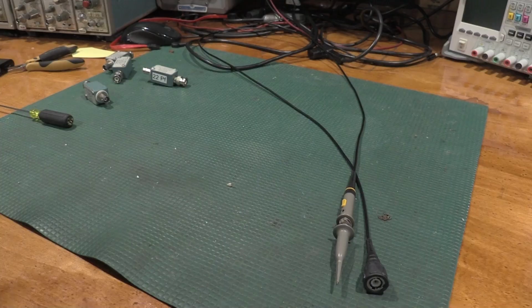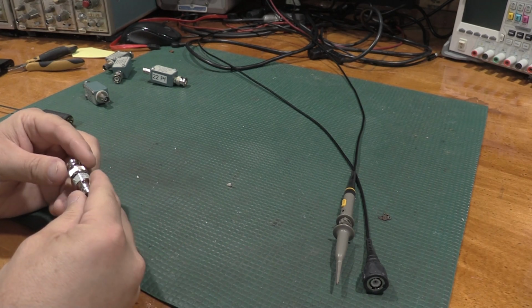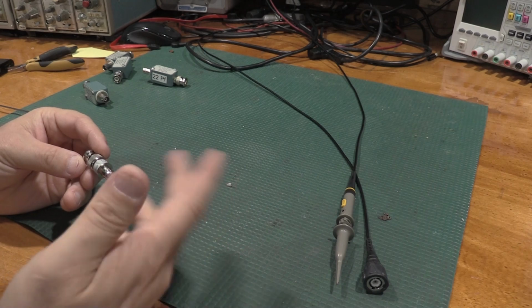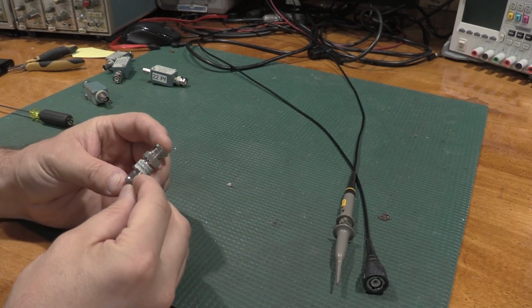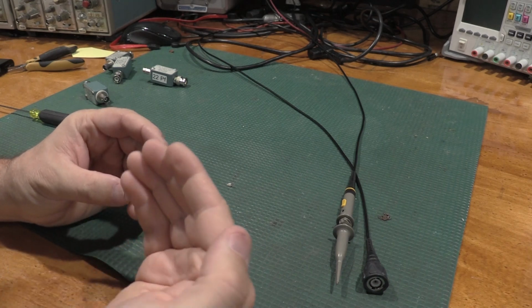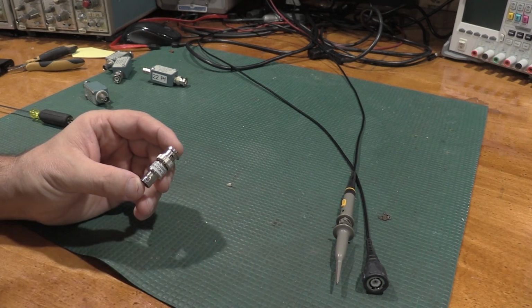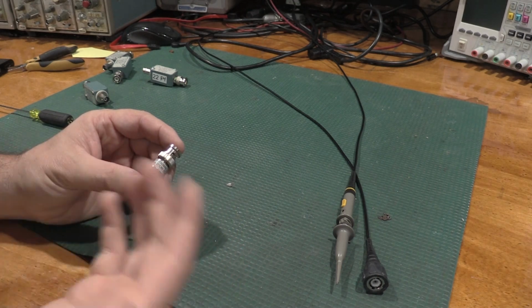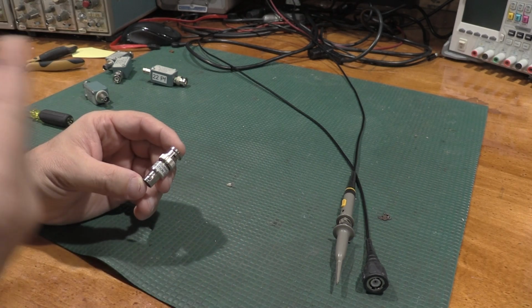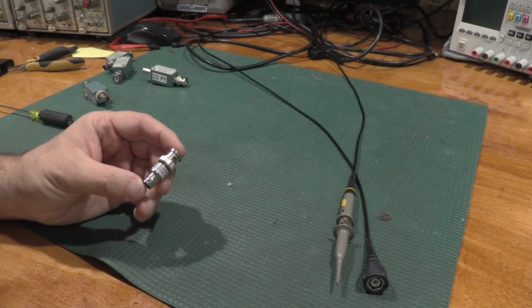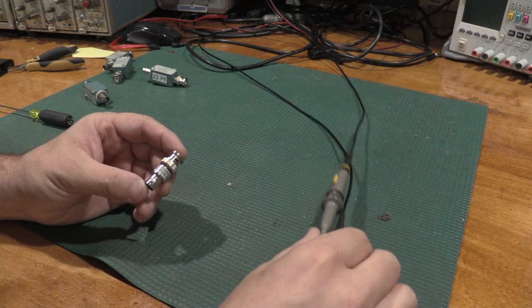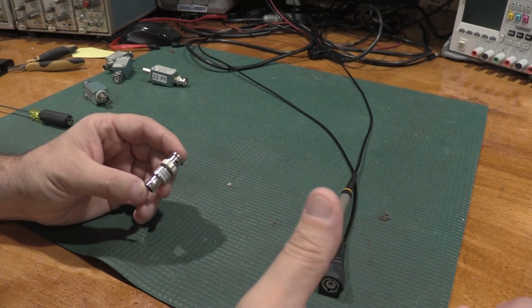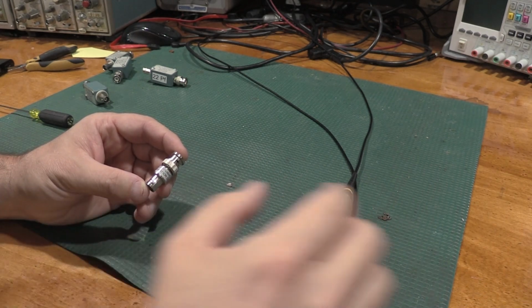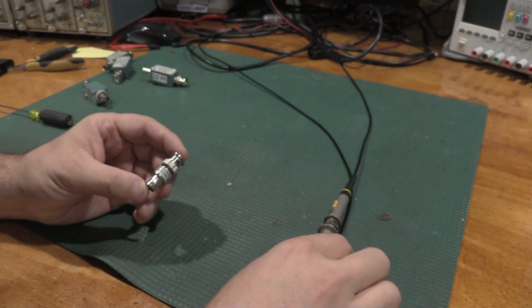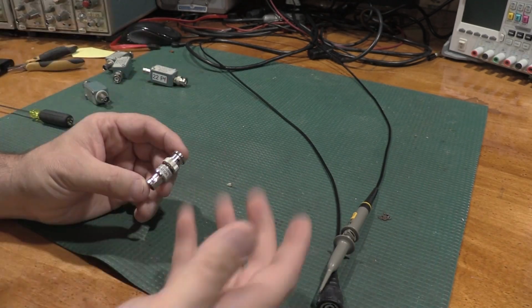If you were doing the in-house alignment and you were setting up the scope to be used primarily in a 50 ohm system where you were doing some high frequency things like that, instead of using the RC normalizer, we would put a 50 ohm terminator on the front of the scope. This isn't a bad thing by any chance. This is just biasing the alignment of the scope for a 50 ohm system versus a high impedance measurement system. If it is set up for 50 ohms, sometimes some probes will not compensate because the input capacitance will be a little too far off. But that's typically okay because when they're set up for 50 ohm systems, they're used with inline serial terminators.